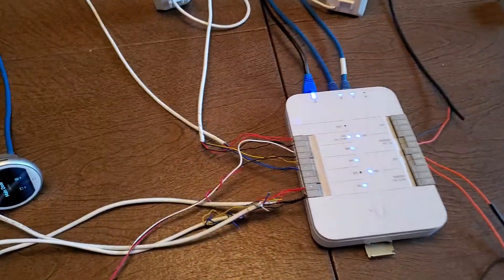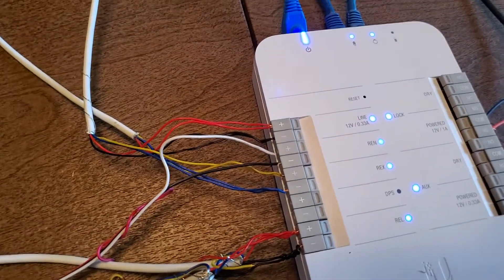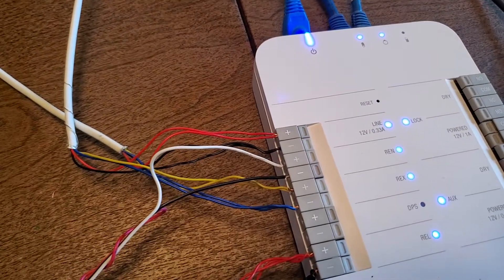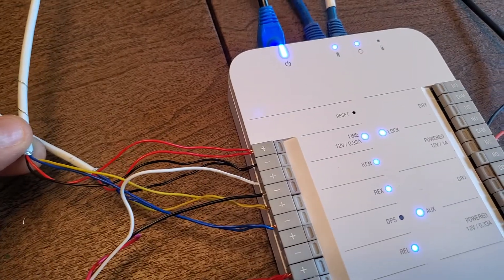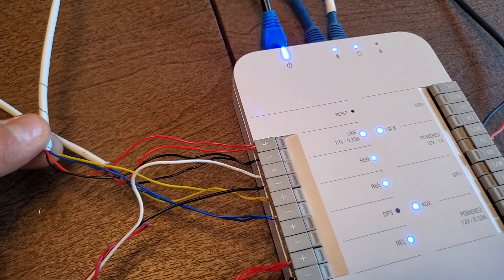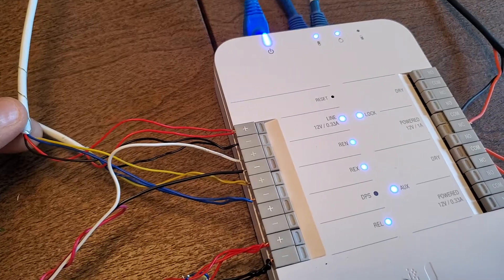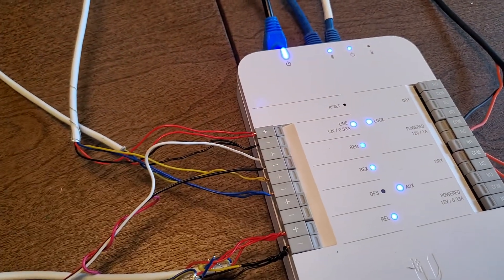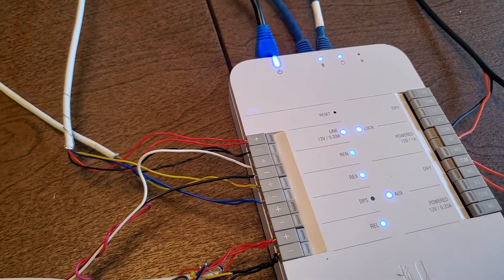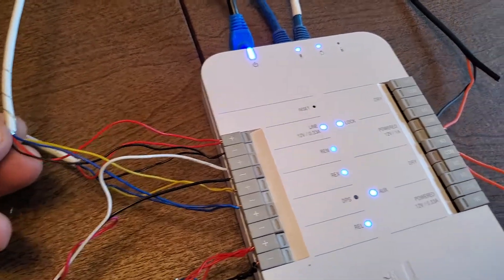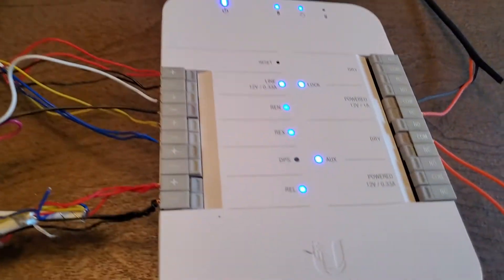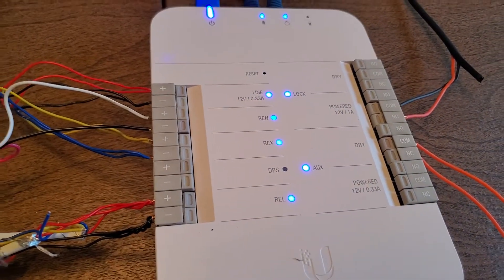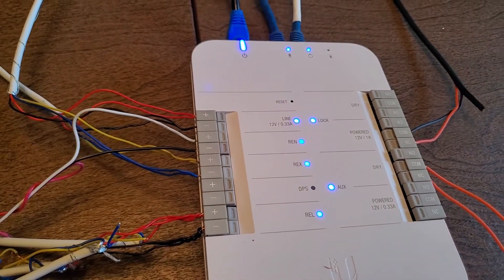Now on my door sensors. What I did is I did, let me zoom here in a little bit. Here is the contacts themselves. So simple, you know, power, negative black, white. And then of course, I ran 22 for gauge, 22 gauge for wire. And in here is where I've run my yellow and my blue. And that'll give me, of course, request to exit, which is what the sensor does.